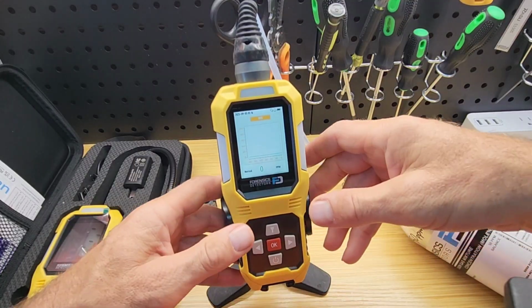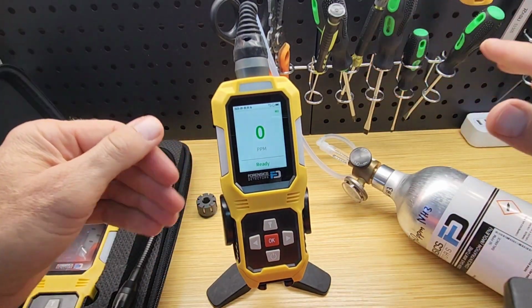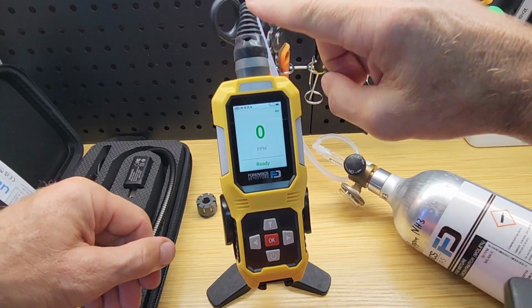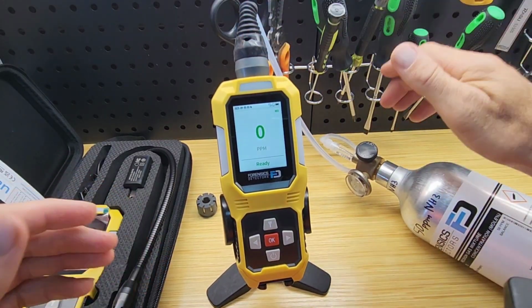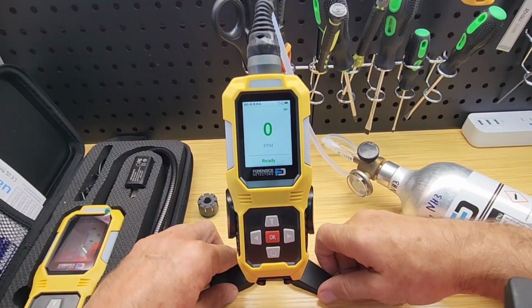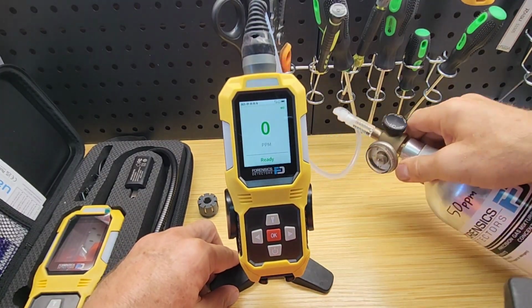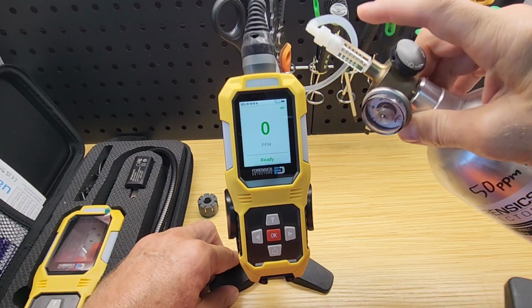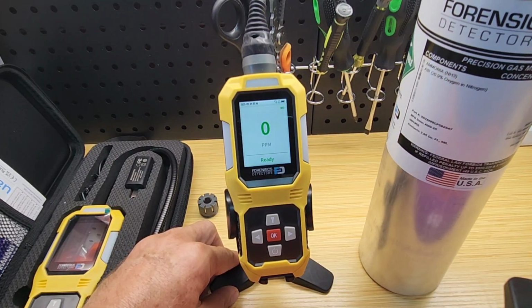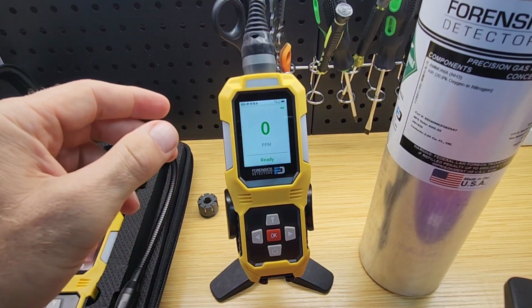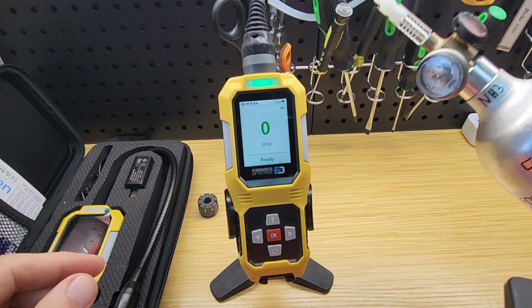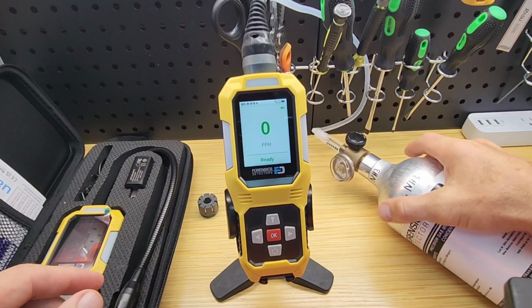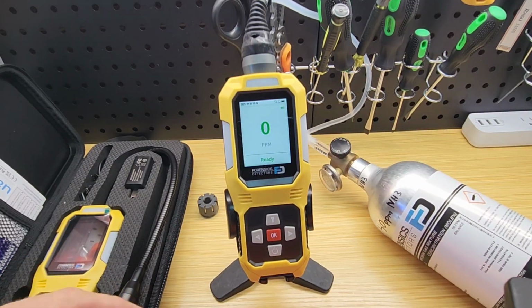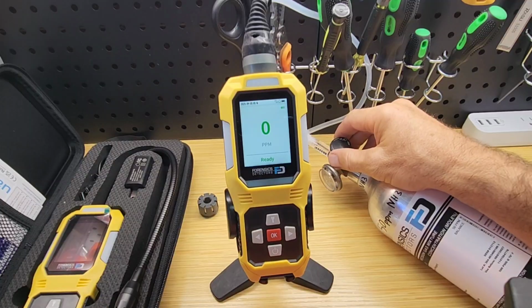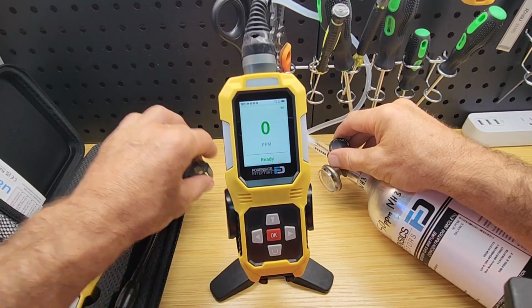Okay, that makes sense. So let's come back to the main screen. 0 ppm. We have our gas. It's all off, and we've attached our gas calibration cap. That is rubber. Now, it's time to expose the unit to our ammonia reference gas, which is 50 parts per million. Now, I'm using our MFV regulator. I'm going to start exposing it and turning it on. I'm going to expose it to 0.5 liters per minute, folks. 0.5 liters per minute. Now, ammonia is a little different to other gases, it takes some time to respond. We need the full 2 minutes for the unit to respond. So we're going to give it some time and we'll come back in about 2 minutes.